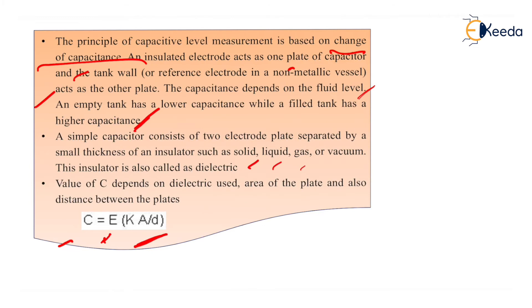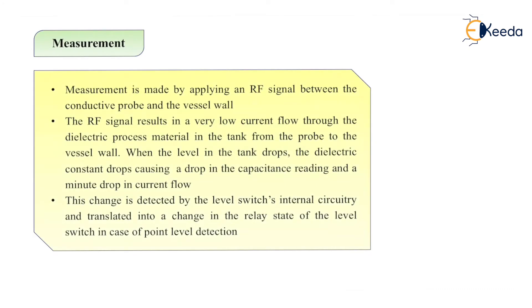The capacitive level measurement works on the principle of change of capacitance. The measurement is made by applying an RF signal between the conductive probe and the vessel walls. The vessel wall acts as one plate of the capacitor and the conductive probe acts as the other plate, forming an electric field in between. The RF signal results in a very low current flowing through the dielectric process material in the tank from probe to the vessel wall.